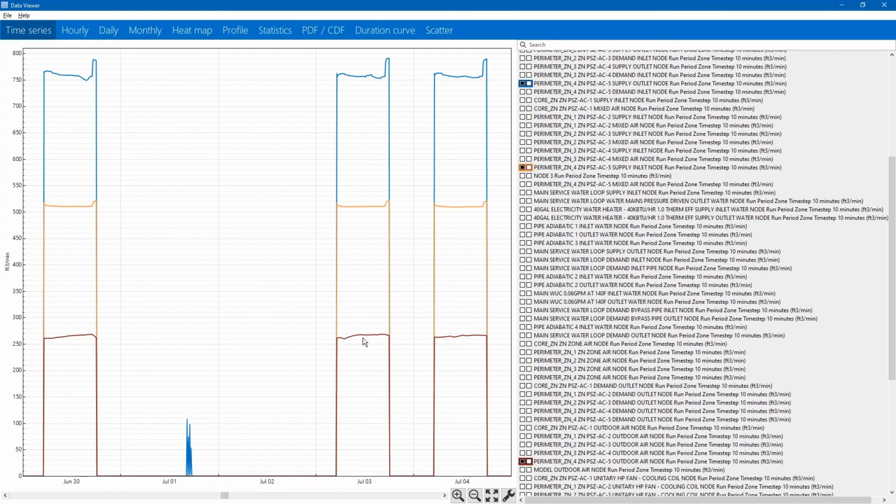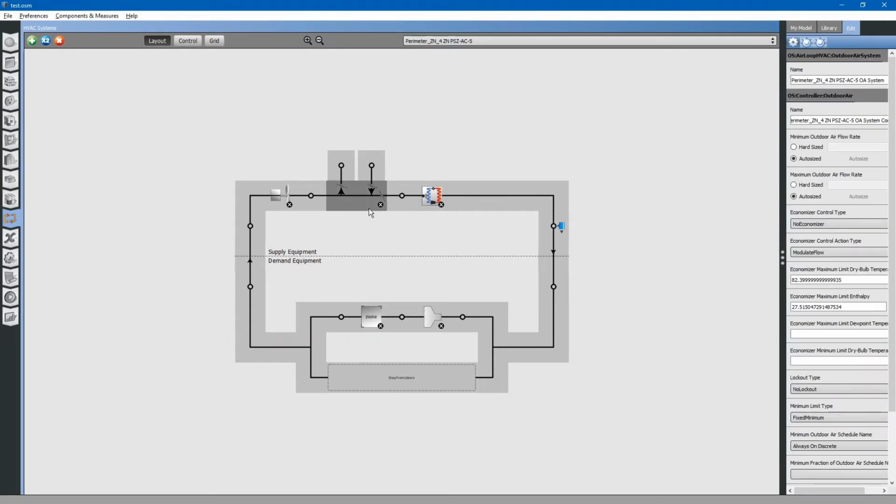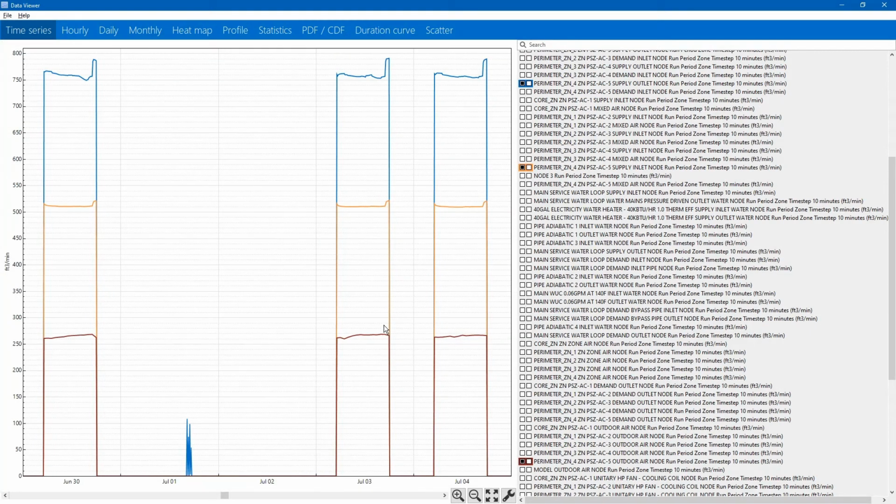And that corresponds to the 250 CFM exhaust fan that we applied to that zone. Now, if we turn that exhaust fan off, you would probably see this ventilation airflow rate dropping lower than the 250. But because that exhaust fan is on and it's operating with the air handler, the outdoor airflow rate in this outdoor air system has to flow a minimum of the 250 CFM for that exhaust fan.